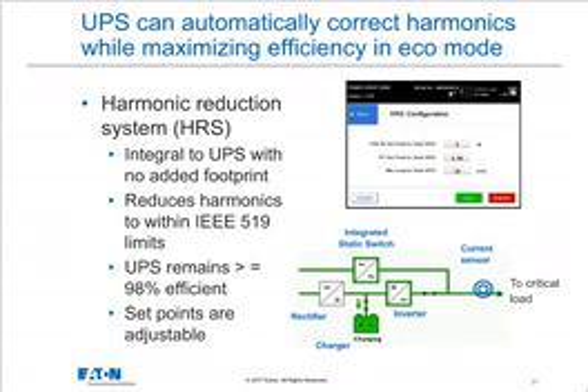However, consider the case where you may have a critical load in a data center, for example, that is very harmonic rich. Now, normally the operation of the UPS on the front of that critical load will act to cancel harmonics and basically isolate the source, whether it be the utility or the generator, from that harmonic rich data center load.